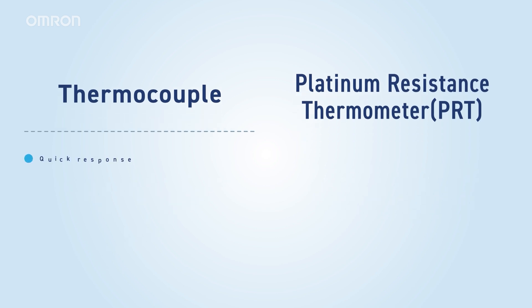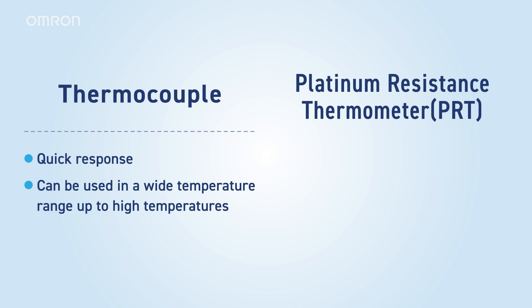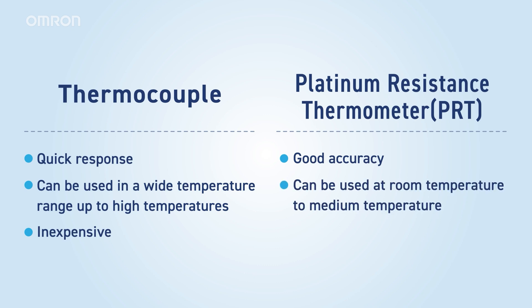Thermocouples have a fast thermal response and can be used over a wide temperature range, including high temperatures exceeding 1,000 degrees Celsius. They are also cost effective, making them widely used in various devices. PRTs offer good measurement accuracy, but are limited to use within the range of normal to medium temperatures. Due to their higher cost, they are used in devices that require high precision, such as scientific instruments and semiconductor manufacturing equipment.